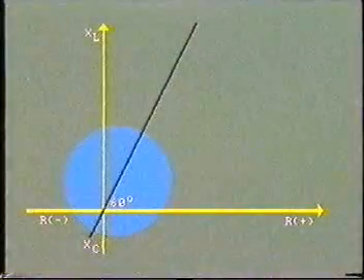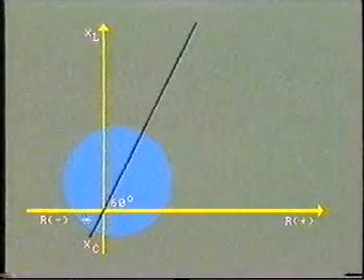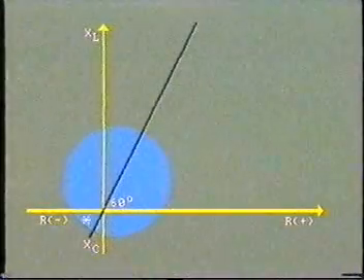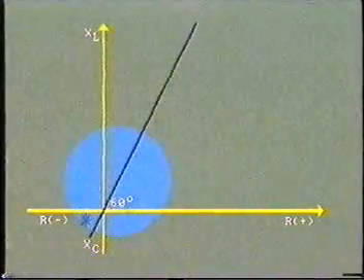For example, a phase fault upstream but close to the bus would provide a very low impedance and probably fall within the circle here and so trip the breaker.